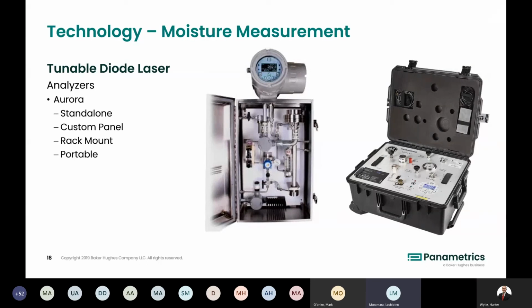There are some other issues that we've seen where we can remotely repair it. It's very rare that there's a hardware failure on the Aurora. That means that it has to come back to the factory. There's a number of ways in the settings to recapture the signal if it loses the water peak for the moisture measurement. And most of the Aurora issues that I've worked on have been resolved remotely, rather than having to send somebody to site and physically take the unit back and get it repaired.